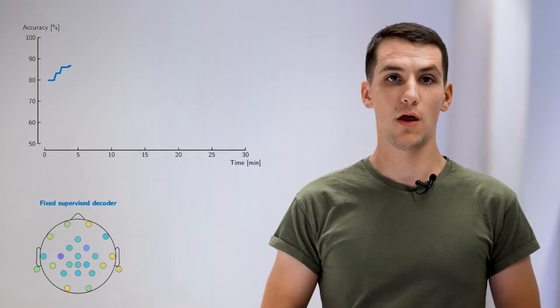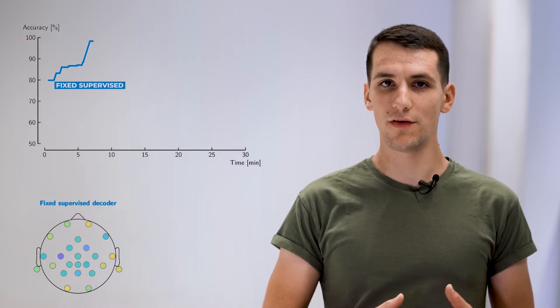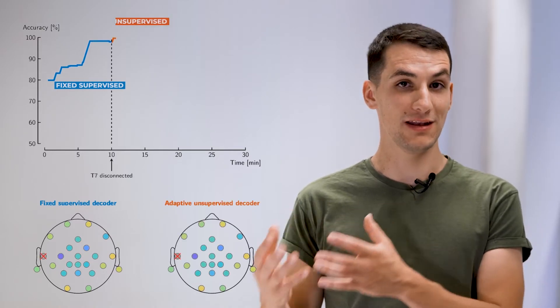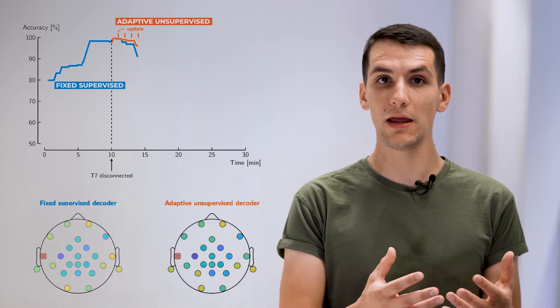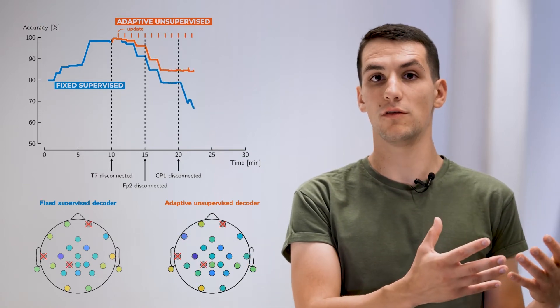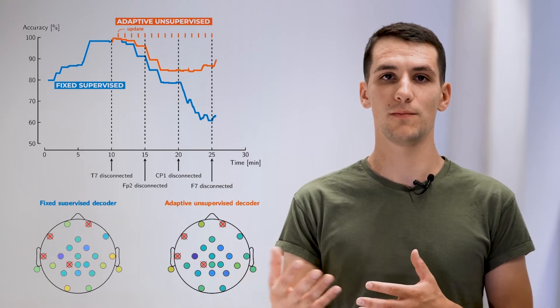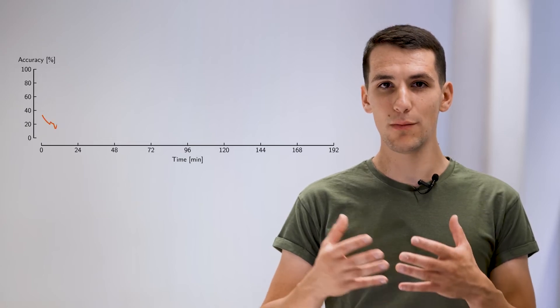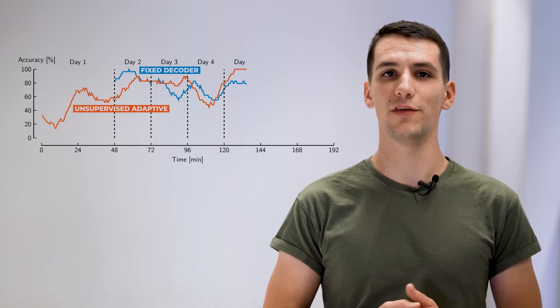The second limitation of the stimulus reconstruction algorithm is that it requires ground-truth data for each new hearing aid user and that it does not adapt to changes in the EEG data over time. To overcome this problem, we have developed an unsupervised and time-adaptive version that is plug-and-play and automatically adapts to non-stationarities in the data, such as electrodes that shift or become loose. The resulting AAD algorithm is tailored to the end application and enables long-term usage of a neural-steered hearing aid.